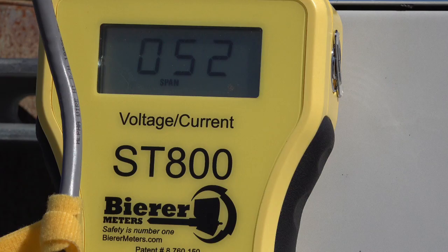It is important to remember that some services may not be able to achieve 800 amps. There are a couple of reasons for this. The conductor size may be too small, such as number 4 wire, or the service may have a long distance causing high voltage drop.